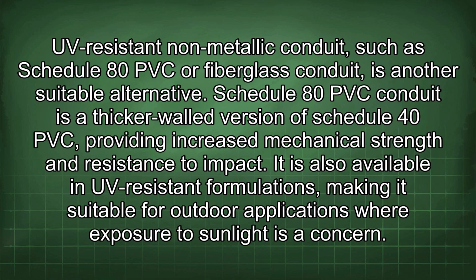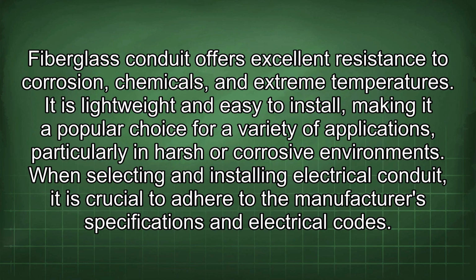UV-resistant non-metallic conduit, such as Schedule 80 PVC or fiberglass conduit, is another suitable alternative. Schedule 80 PVC conduit is a thicker-walled version of Schedule 40 PVC, providing increased mechanical strength and resistance to impact. It is also available in UV-resistant formulations, making it suitable for outdoor applications where exposure to sunlight is a concern. Fiberglass conduit offers excellent resistance to corrosion, chemicals, and extreme temperatures.